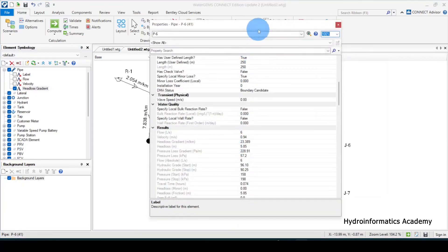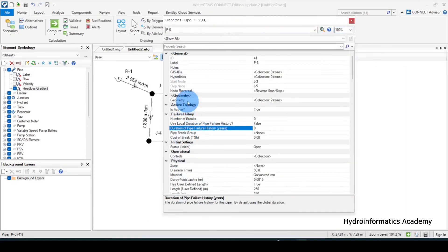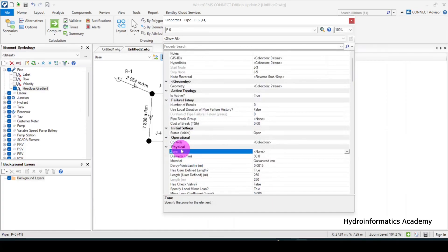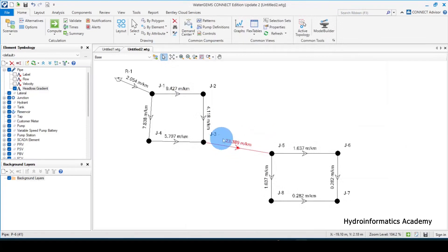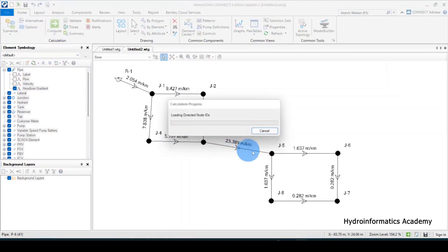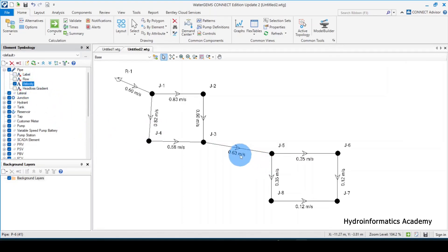To reduce head losses, I'll increase the pipe diameter. Let me double-click the pipe and find the physical pipe diameter. I'll increase it to 110 and run the model. You can see the head loss gradient went from 23 all the way down to 8. The velocity for that pipe is now 0.6 — a good result.